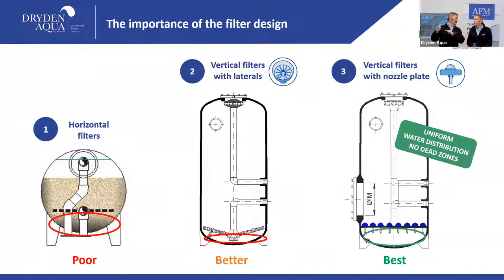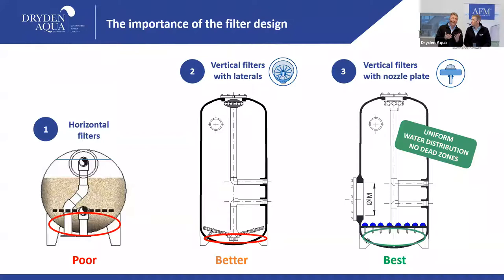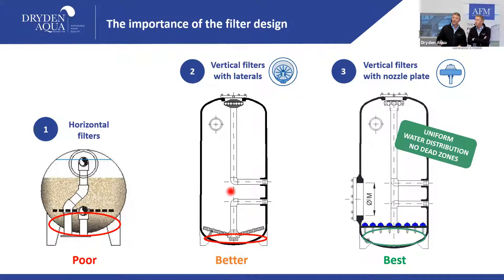Nozzle plates are required whenever you do an air wash, which is used with sand filters to rub off biofilm at 60–90 m/hr. With AFM you don't need this since there's no biofilm. If you use air wash with laterals, all the air exits in the first five centimeters — you just disturb the filter bed and make a mess. Never use air wash with laterals. Nozzle plates also ensure equal water distribution during both filtration and backwash.